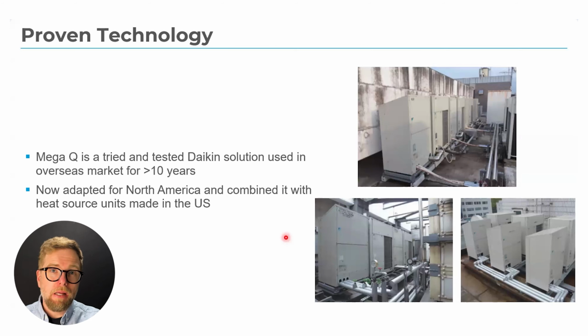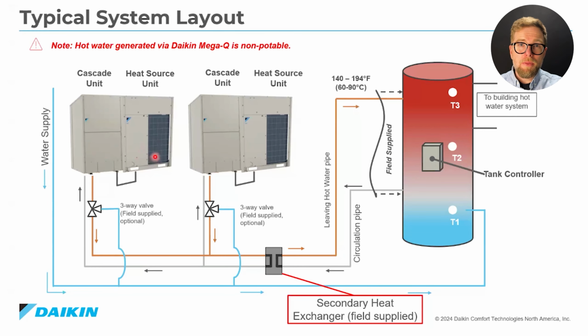Daikin currently has pilot projects in New York City, and they've tested these systems through freezing temperatures, and some even added backup electric heaters inside the storage tanks, which they never even needed to switch on. That's reliable performance with tangible data behind it. So if you're based in New Brunswick or Nova Scotia or Prince Edward Island, and you've been hit with questions about electrifying domestic hot water or needing to replace old boilers, this is a game changer that you can confidently propose. Let's zoom in on exactly how the Daikin MegaQ generates hot water so efficiently.